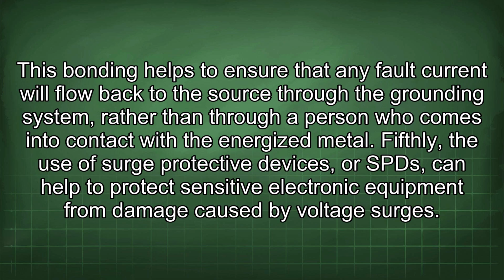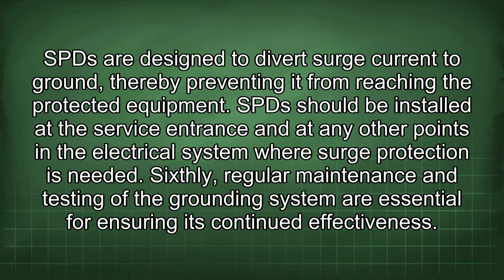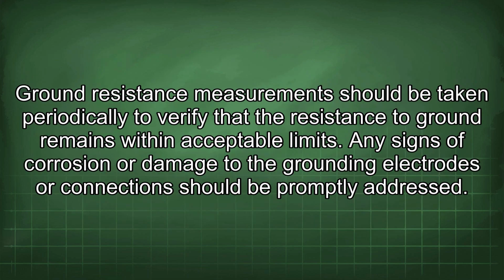Fifthly, the use of surge protective devices, or SPDs, can help to protect sensitive electronic equipment from damage caused by voltage surges. SPDs are designed to divert surge current to ground, thereby preventing it from reaching the protected equipment. SPDs should be installed at the service entrance and at any other points in the electrical system where surge protection is needed. Sixthly, regular maintenance and testing of the grounding system are essential for ensuring its continued effectiveness. Ground resistance measurements should be taken periodically to verify that the resistance to ground remains within acceptable limits. Any signs of corrosion or damage to the grounding electrodes or connections should be promptly addressed.